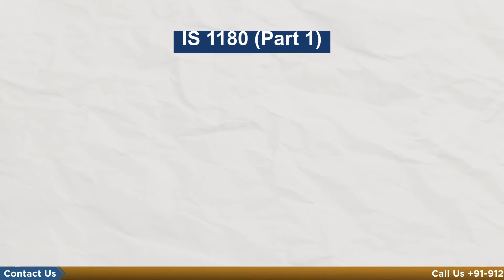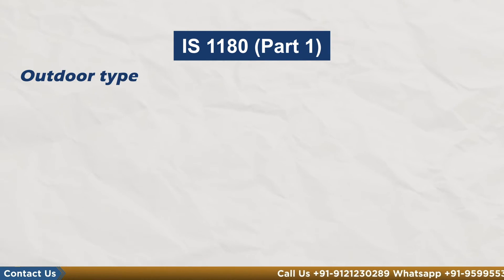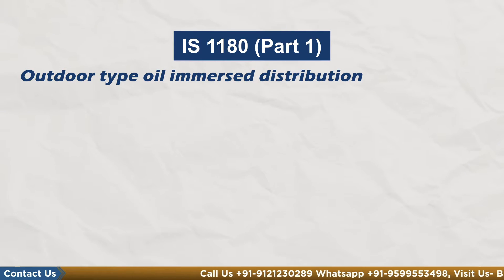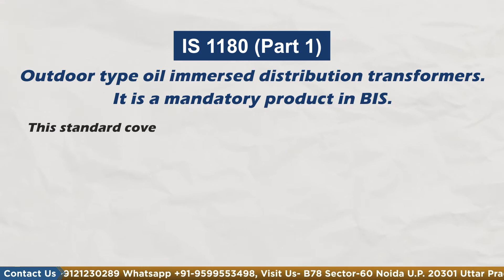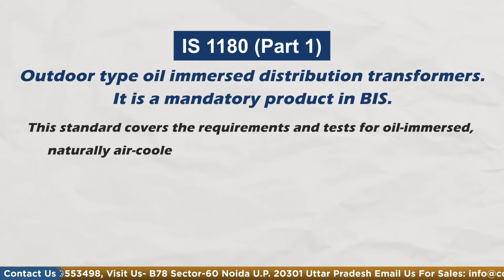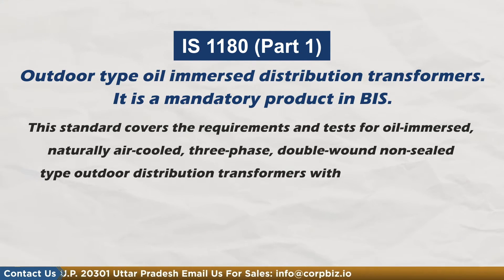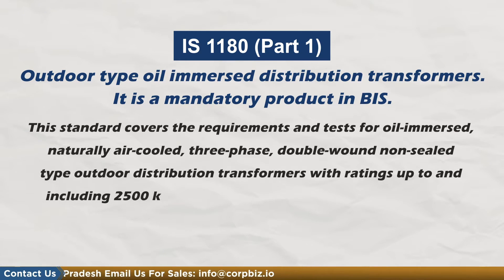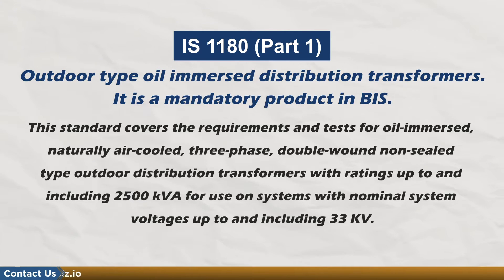Let's take a closer look at IS1180 Part 1 for Outdoor Type Oil Immersed Distribution Transformer. It is a mandatory product in BIS. This standard covers the requirements and testing for oil immerged, natural air-cooled, 3-phase, double wound non-sealed type outdoor distribution transformer, with rating up to and including 2500 KVA, for use on systems with nominal system voltage up to and including 33 KV.